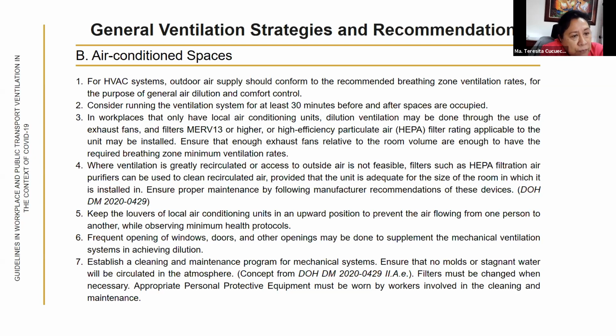So if you have local air conditioning only, dilution ventilation may be done through the use of exhaust fans and filters MERV 13 or higher. If it's not a full air handling unit, and it is just local air conditioning, the supply of air through the air conditioning unit will have to be removed through the exhaust fans. And that is why we are saying that these are very important details that you should consider.